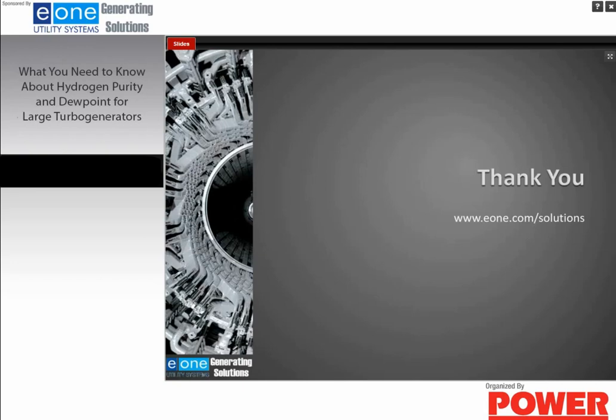Okay. What is more accurate, thermal conductivity or vibrating element density meters? That's a very good question. It depends on the thermal conductivity analyzer that you're using. I'm speaking now as a salesman. The Environment One analyzer, as far as thermal conductivity, is one of the better ones on the market. It's very stable and very accurate. That being said, Yokogawa's vibrating element analyzer is also very accurate and very stable. I would actually put our analyzer and the Yokogawa analyzer in the same class, of equal accuracy and equal stability.